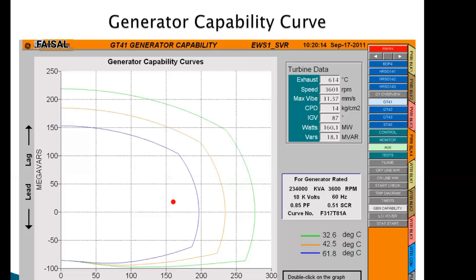In that case we have to receive that reactive load, so we will run our generator in under excitation mode and the dot will come below this zero line in the negative side. But on the negative side we cannot receive much megawatt. The curve is very near, but on the positive side you can take up to here, 100 megawatts.